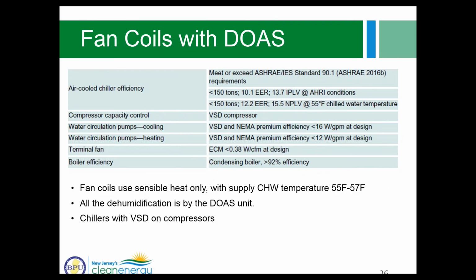And then another option for HVAC system design is fan coils with dedicated outdoor air system, and this we do see on projects. So again, important considerations are pump power and fan power. There are targets that you can see on the slide for chilled water pumps and hot water pumps, also targets for fan powers for terminal units. ECM motors should be specified with fan power less than 0.38 watt per CFM.